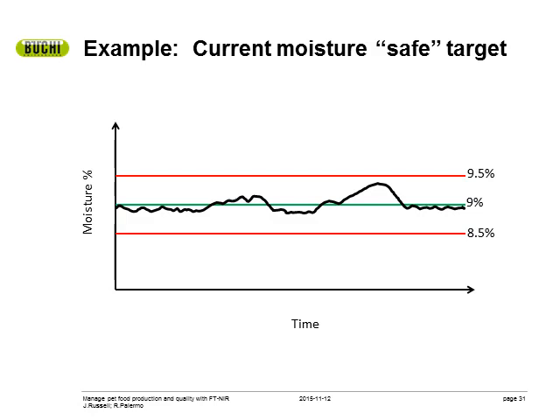Without a continuous monitoring scheme, production has to be extra conservative with their targets and limits. Here, the upper production control limit is set to 9.5% moisture to allow some deviation without risking out-of-spec material. Out-of-spec material would be anything above 10% moisture.